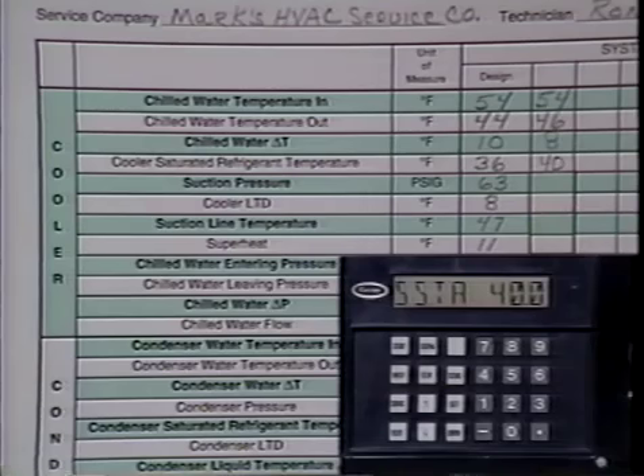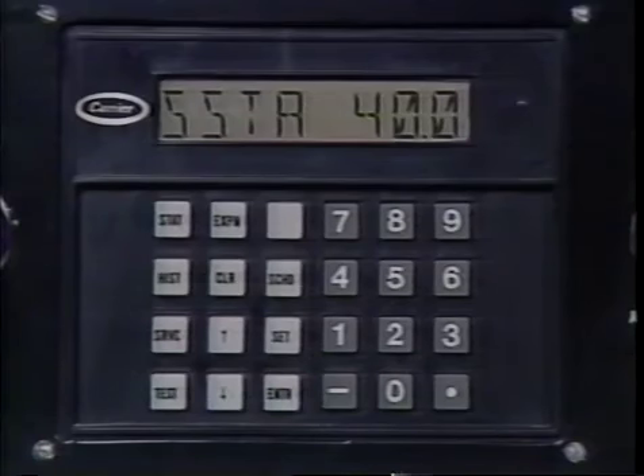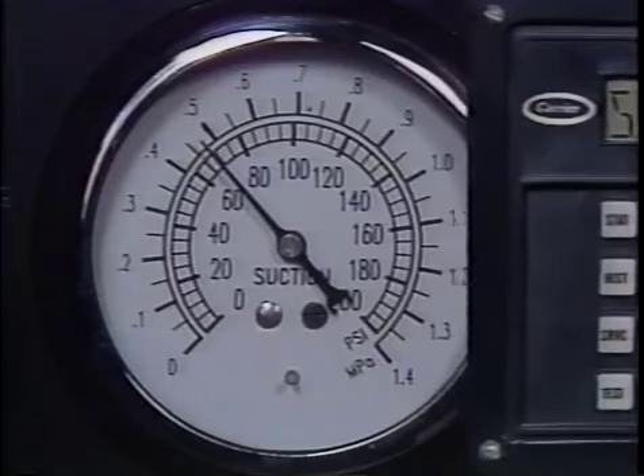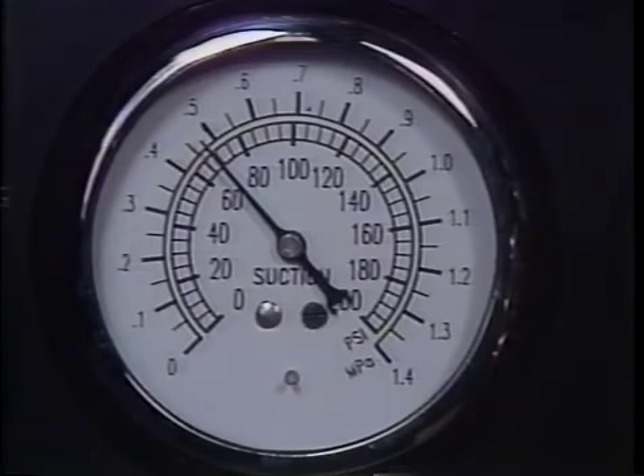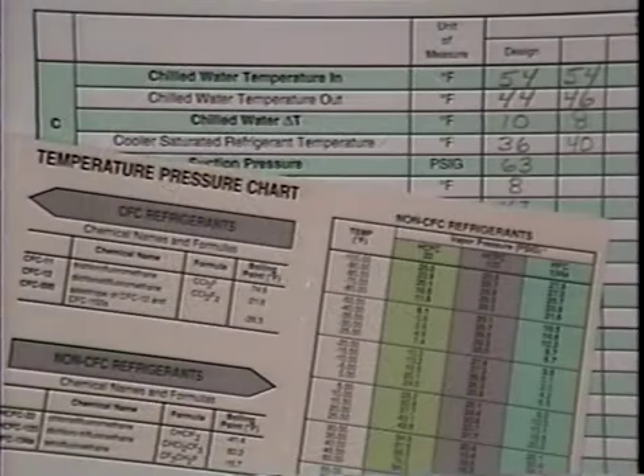If the cooler saturated refrigerant temperature is at 32 degrees or lower, then the possibility of a freeze-up exists. If you cannot measure the actual cooler saturated refrigerant temperature, then the saturated temperature corresponding to the suction pressure may be used as the actual cooler refrigerant temperature. This temperature is required for determining the cooler leaving temperature difference.